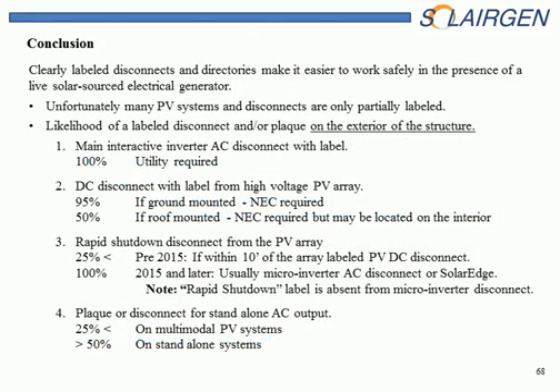Clearly labeled disconnects and directories make it much easier to work safely in the presence of a solar-sourced electrical generator, a PV system. Unfortunately, a lot of systems are not properly labeled. So what is the likelihood that you will see a labeled disconnect or a plaque on the exterior of the structure? If it is the main inverter AC disconnect, 100%. The utility requires that you cannot connect up an interactive inverter without it.